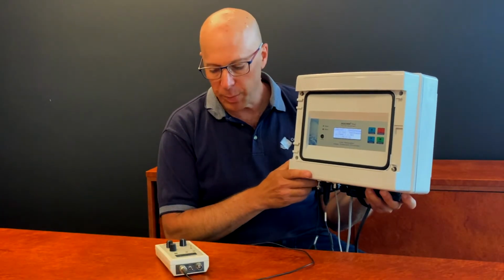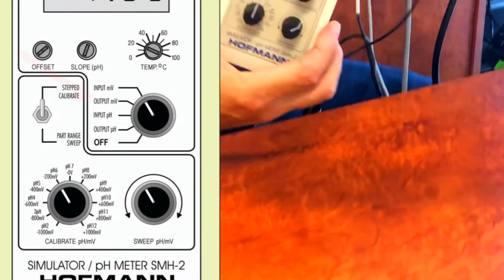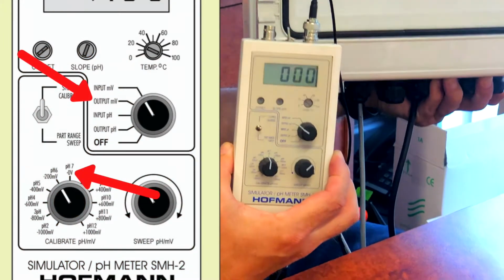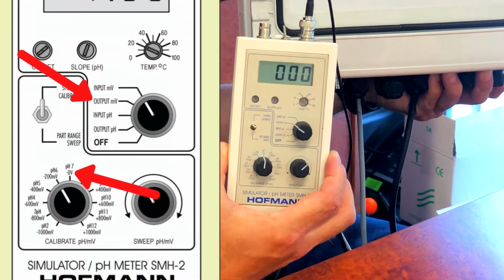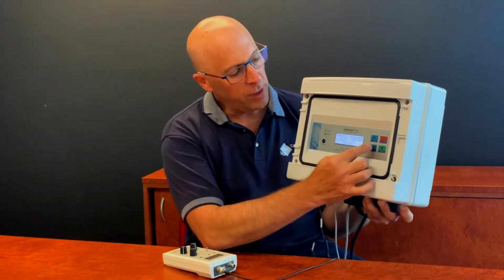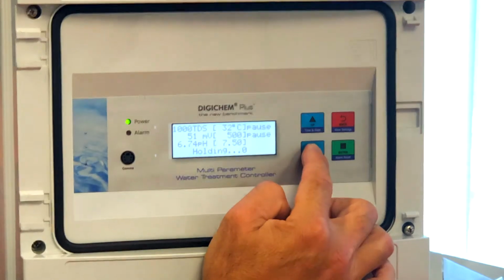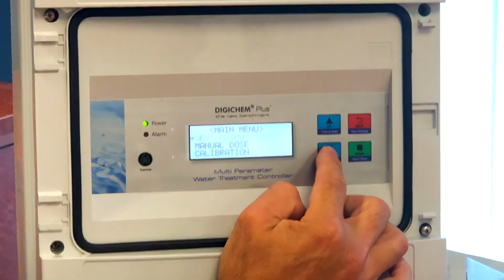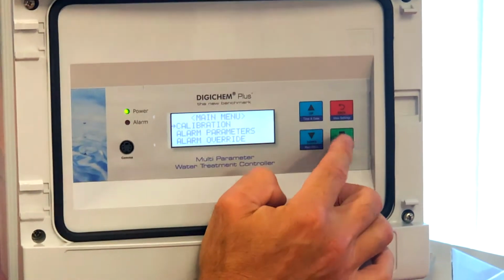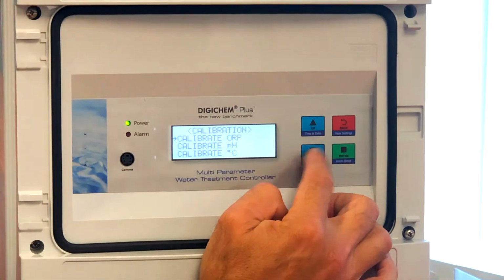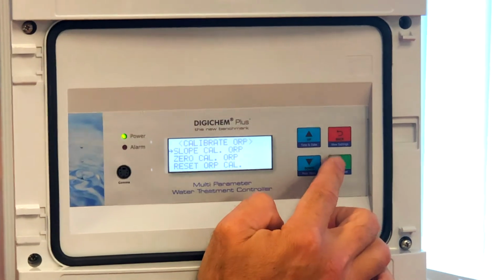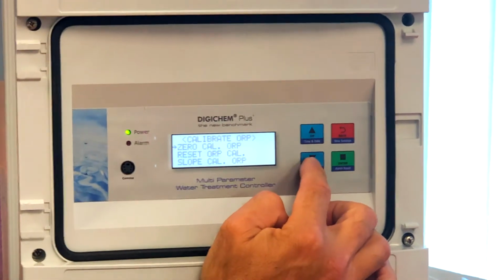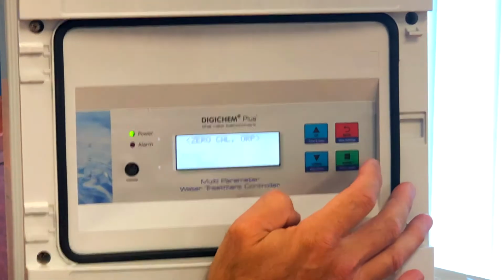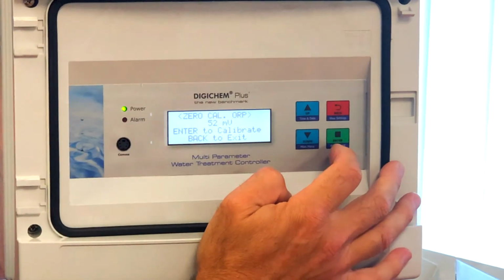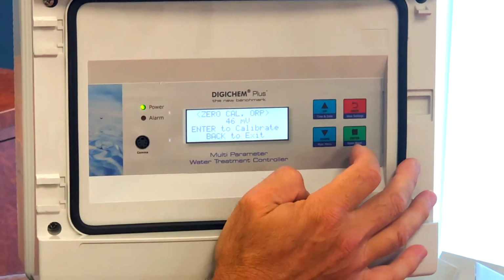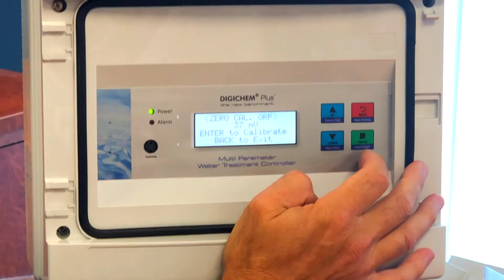Okay, first step is to set the simulator to output 0 millivolts. As you can see on the simulator, it's reading 0. We then go into the menu of the controller and we go down to calibration, press enter. We go to ORP calibration, press enter. We go to 0 calibration, press enter. We wait for the reading to settle down and then we press enter.